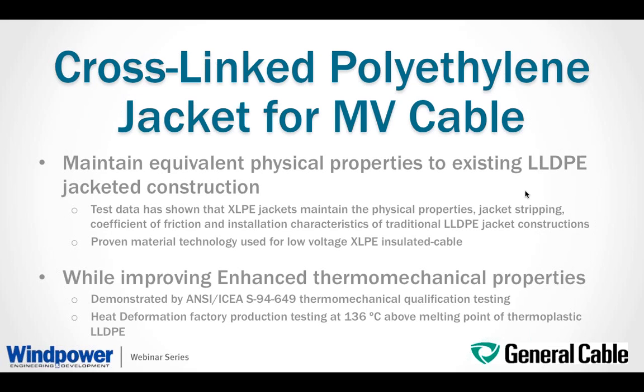So it is a material that is compatible with the extruded semiconducting insulation shield. It's normally applied as an extruded tube-fill jacket encapsulating the neutral wire. So this allows for a robust design that can be easily sealed for longitudinal water penetration resistance.